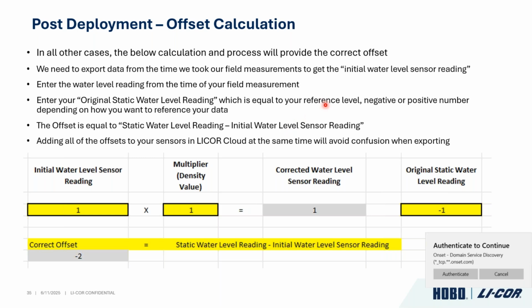So what you want to do, because if you're using a longer cable, you're not going to measure out that cable. It's too long. You wouldn't be able to do it. And so what you can do is go into LI-COR Cloud. You can go to your exports, and you can export the data from those water level sensors so that you can get your initial water level reading. So at the time that you took your reference measurements or your static water level readings, it will tell you this is what the sensor was reading at that moment in time. And then at that point, you want to take your original static water level reading. So, again, if we're talking about groundwater, what was your water level reading in relation to ground at that moment in time? Maybe it was -1. It was a foot below ground surface. That would be your original static reading.